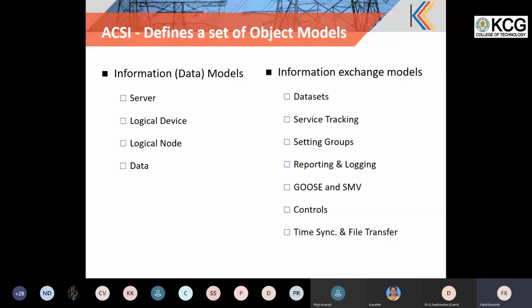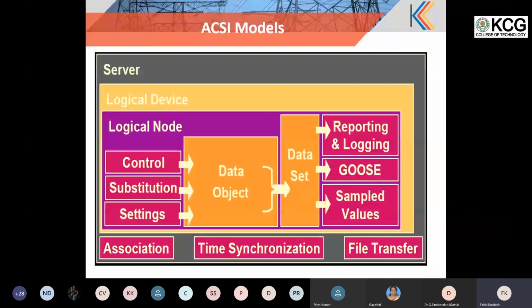So what we have is a server, that is every IED is a server, and under the server you can have multiple logical devices, like a logical separation of data is given under the logical device, and under that you have specific functionality named under the logical node, and under the logical node you can have a control model, that is you can issue a control command, operate directly on the logical node and its data object element.